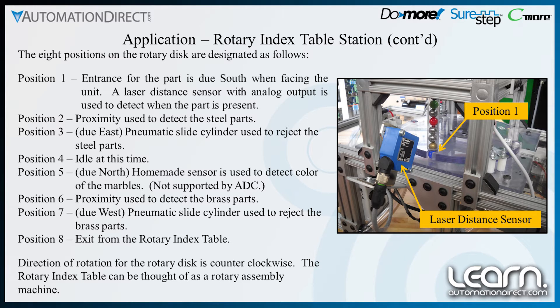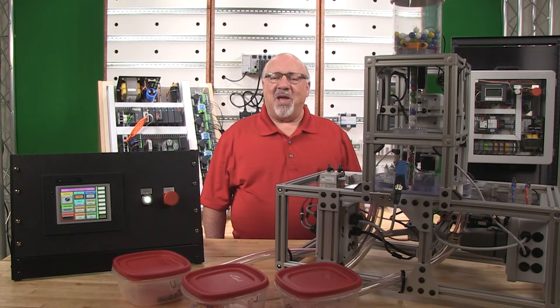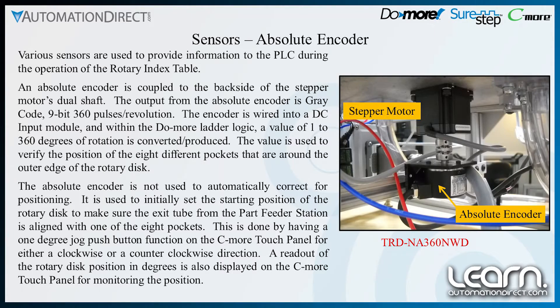The rotary index table can be thought of as a rotary assembly machine. Various sensors are used to provide information to the PLC during operation. An absolute encoder is coupled to the back side of the stepper motor's dual shaft. The output from the absolute encoder is grey code, 9-bit, 360 pulses per revolution. The encoder is wired into a DC input module, and within the DoMore ladder logic, a value of 1 to 360 degrees of rotation is converted and produced. This value is used to verify the position of the 8 different pockets around the outer edge of the rotary disk.